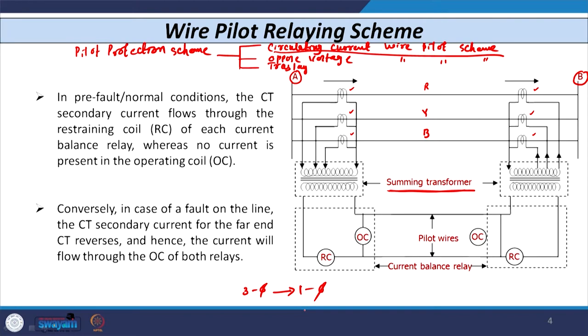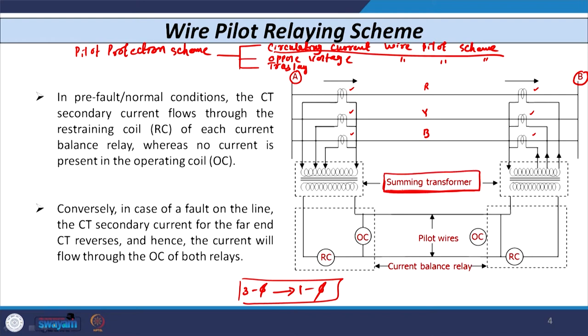Why use a summing transformer? Whenever we have to transmit a signal from substation A to substation B, we need to lay down physical pilot wires. If we had to lay down three wires for three phases, that would be very costly. That is why in actual field practice, the three-phase quantity is converted into a single-phase quantity using the summing transformer.